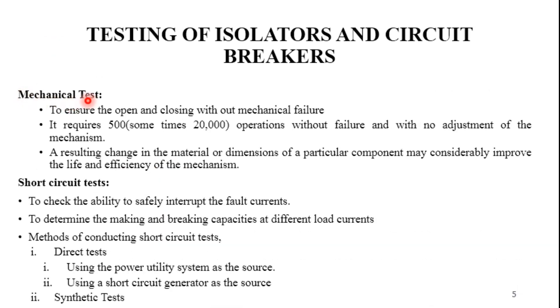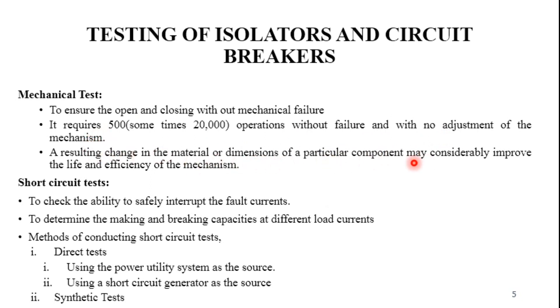The mechanical test is done to ensure the circuit breaker opens and closes without any mechanical failures. It requires at least 500 operations without any failures, and sometimes up to 20,000 operations with no adjustment of the mechanism. Any change in material or dimensions of a particular component may considerably improve the life and efficiency of the mechanism.